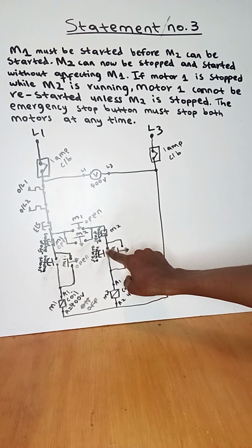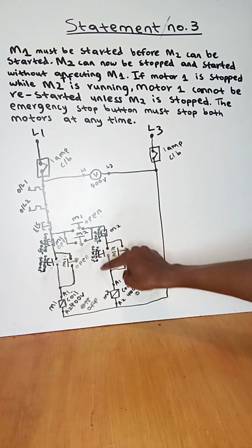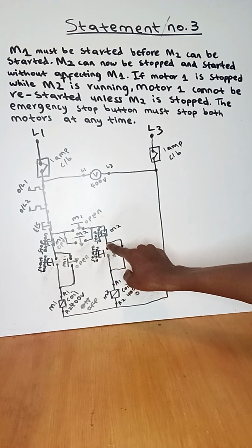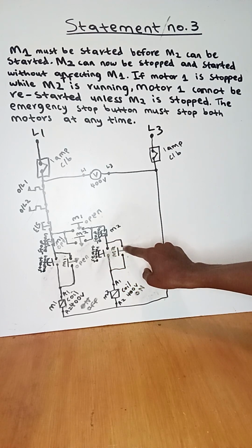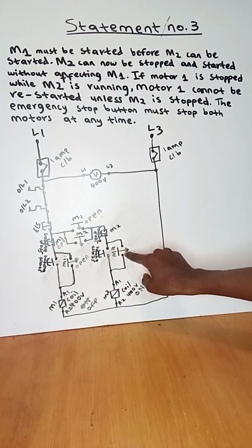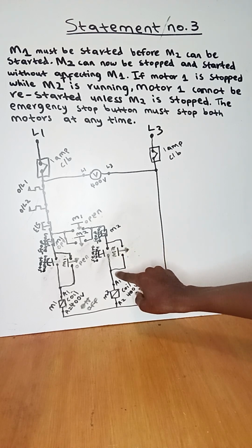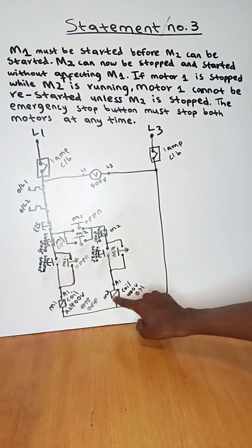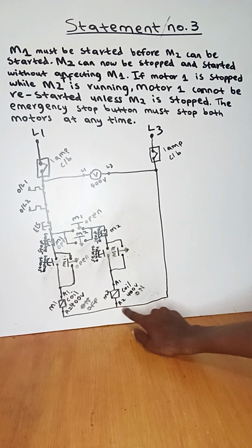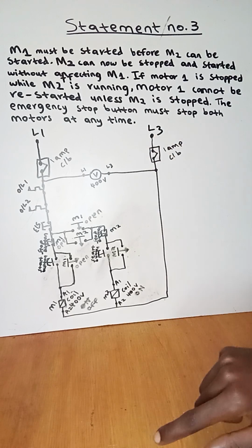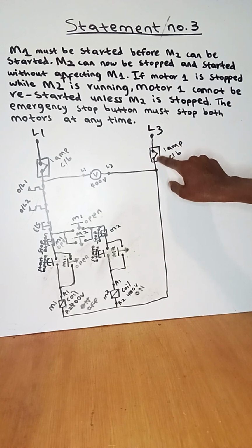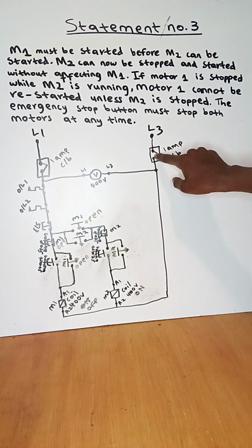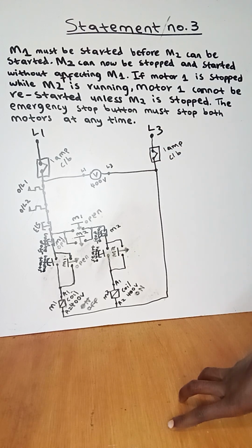From here, the start button is normally open, which means current cannot flow through the start button, but current also bridges to the retainer of motor 2 and finds it normally closed, current flows all the way to A1 of the coil of motor 2. But let's check from A2. A2 also gets live 3 because current will also pass through the closed contact of the circuit breaker.